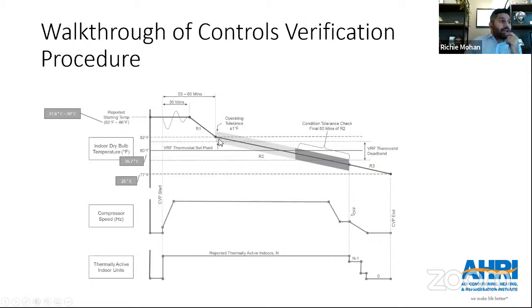After that, you want to elongate the temperature ramp down as much as possible, but within a certain range, such that you're able to get enough effective data in the best case possible. The slower you make this ramp down, the more precise your data readings can be. This slow ramp down goes on until you see your first indoor unit shut off. When your first indoor unit shuts off, you have a 60-minute period from that point on during which your data readings are going to be used for the purpose of the CVP.